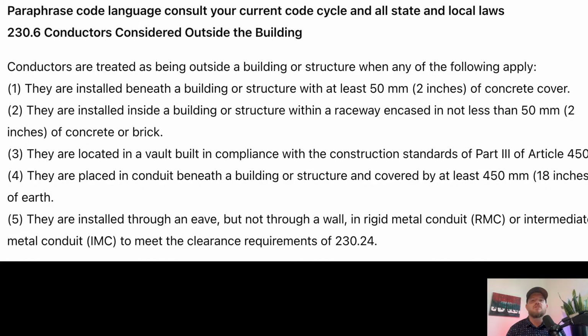Conductors considered outside of a building. Why would we need to know if a conductor is considered outside of a building or not? Well, there's several codes - it could be to do with burial depth, it could be to do with the service entering the structure at the nearest point. There's a lot of different codes, and other things like the type of wire we're using, that depend on whether or not it's outside of a building. So there are many codes that kick in whether or not these conductors are inside a building or not. Let's take a look at the 5 ways they are considered outside of the building.